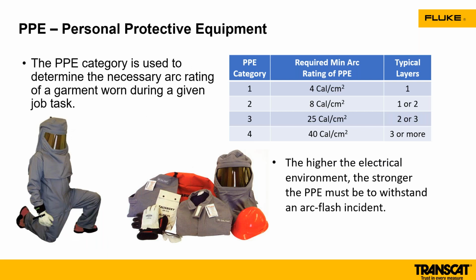When you look at that, it gives you information. It tells you what type of PPE you need to wear and what is that environment. The PPE category ratings are necessary based on the potential energy that you're working on. Sometimes when you're working around a 120 volt residential outlet, something of that nature, you don't necessarily need to have that 40 cal suit, but you do need to have the right equipment on, even if that's considered a category 1. It's based on the layers, it's based on that protection for you if potentially a fault should happen. So again, this is really key information. Part of NFPA says that all of the technicians should be trained. You need to be trained in your environment and trained with the equipment that you're working with, i.e. your meter. You need to know how to work your meter correctly and work in those environments.